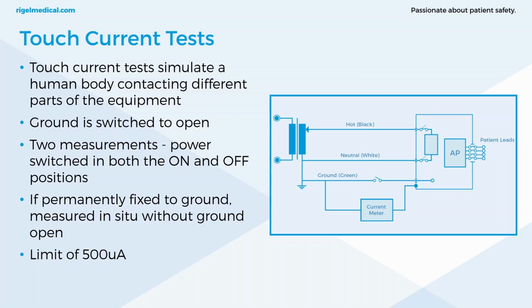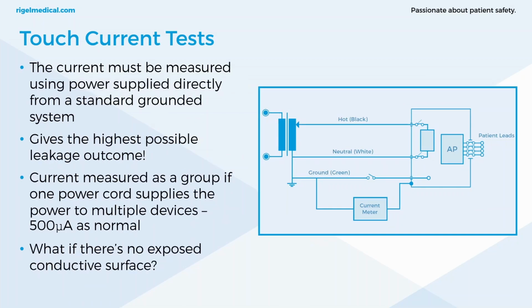If the appliance is fixed to ground, then it's measured in situ without the ground open. The current must be measured using the power supply directly from a standard grounded system. This gives the highest possible leakage outcome. Now, we went over this in one of the previous slides for TN systems. Of course, we know that a good feature with the Rigel products is the auto detection of this TN standard system.